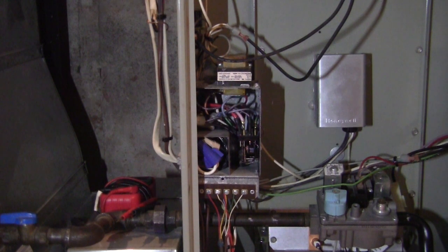Okay, let's talk about how the unit works by temperature control. We all know we have a control panel. Usually it's on the main floor. You have either the old style or the modern. Right now I see some families that have some kind of Bluetooth controller. It doesn't matter what. Let's talk about the heater, not the air conditioner.